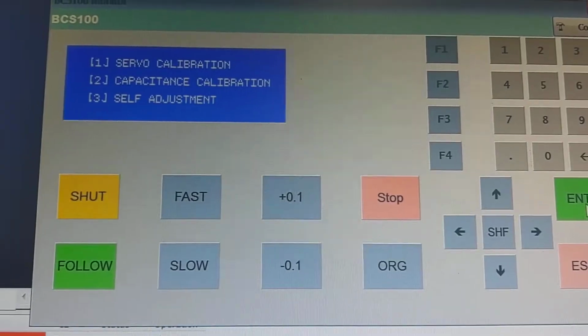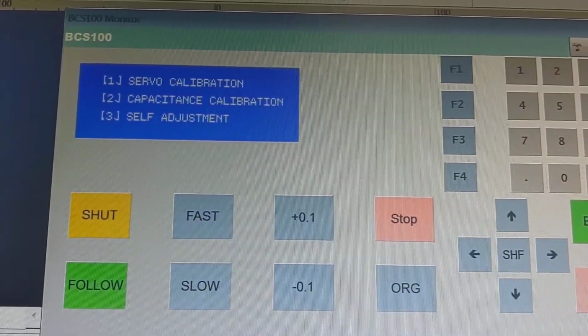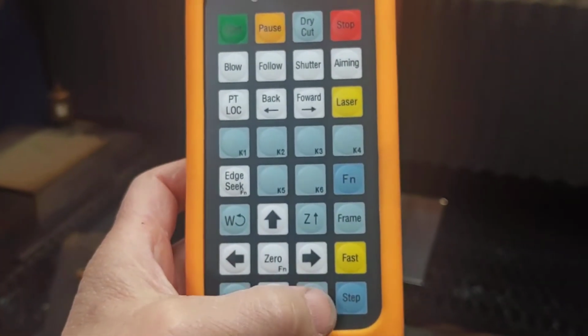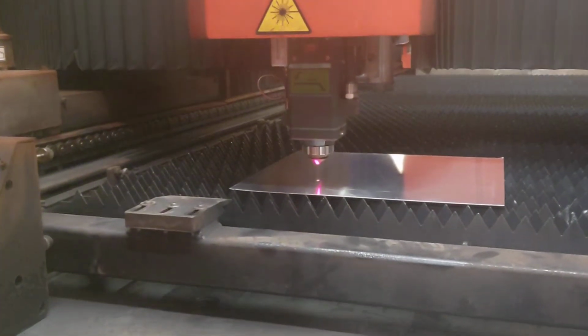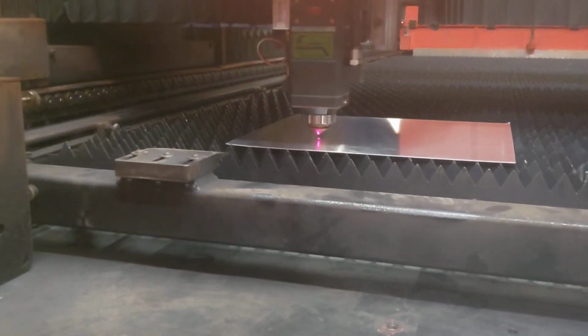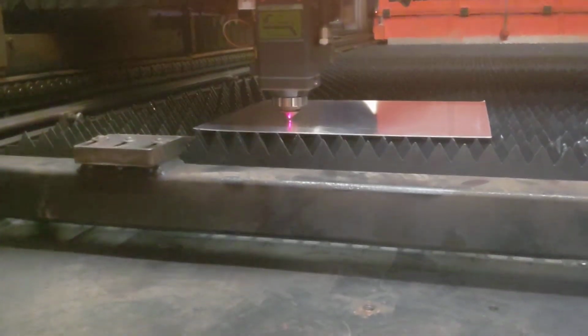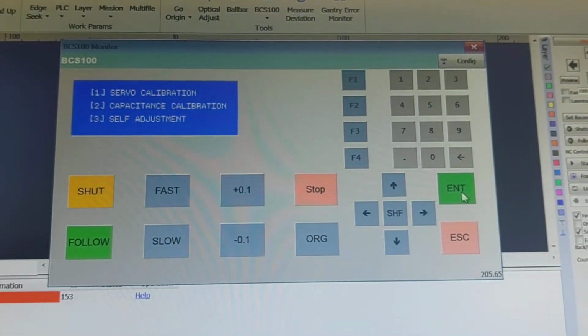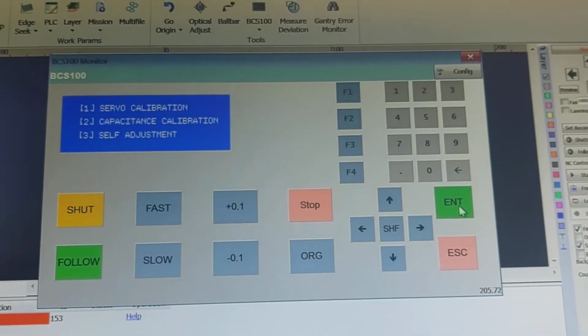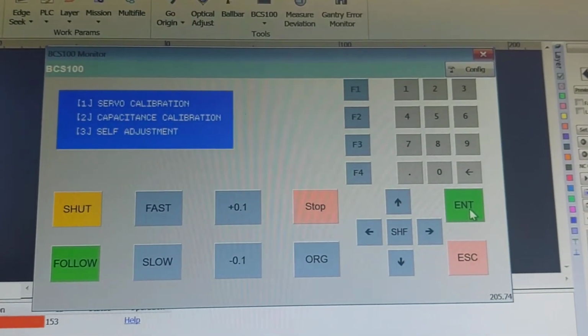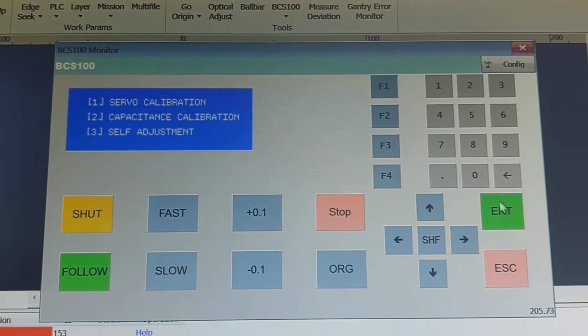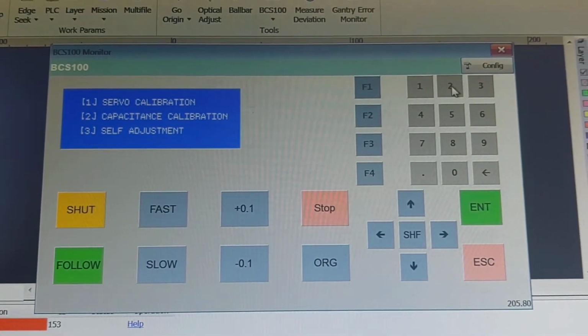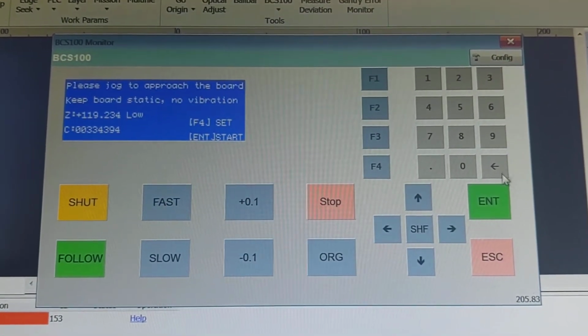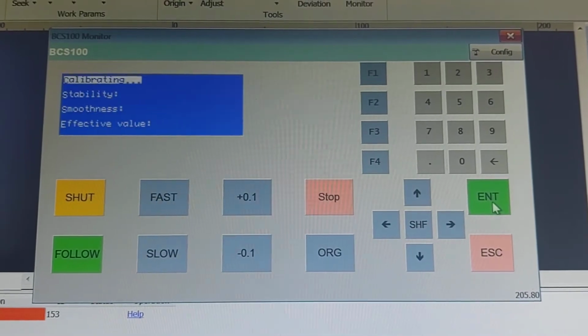The next procedure is capacitance calibration. Back with the remote pendant, jog the Z so it's about a 1/16 off the plate. Right about there. The lower you have it, the more accurate the calibration will be. So have it around a 1/16 if possible. Click on 2. Enter to start the calibration process.